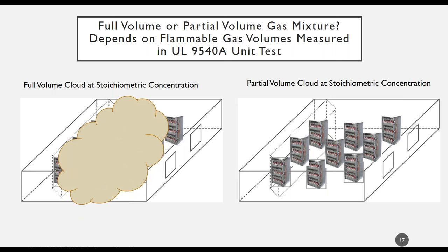You see on the left that a full volume of flammable gas has now been generated in the BESS on the left. And subsequently, there's going to be an ignition that's going to threaten that enclosure unless the panels shown on the right wall are open early enough and are adequately large to relieve the pressure and prevent the damage threshold pressures from occurring. Next, please.